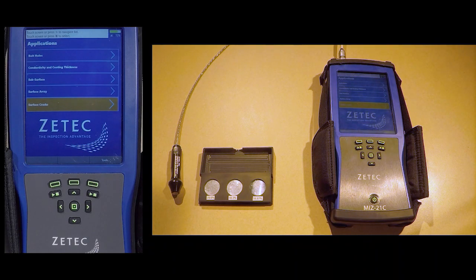The calibration wizard and intuitive interface makes the MIZ-21C easy to use for conductivity measurements. In order to properly calibrate the MIZ-21C, an approved conductivity standard is needed in the IACS range of the material to be tested, along with an appropriate size probe.